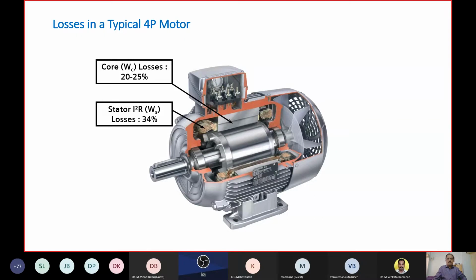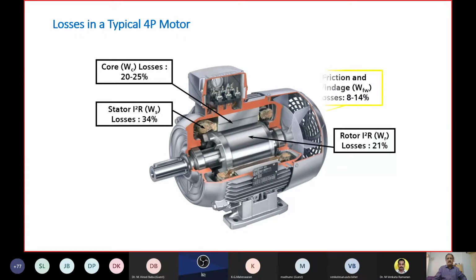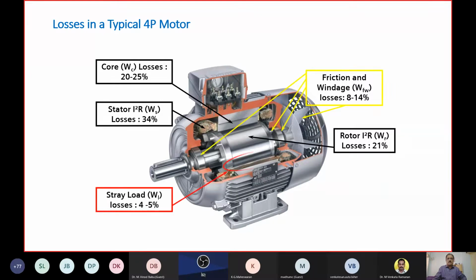Now, what are the typical losses? Most of you in the education field, academic field, will know these are the typical losses in a motor. You have core losses, which is iron losses, which contributes approximately 20 to 25% of the total losses. Stator I squared R, or stator copper losses, is approximately 34%. Rotor losses or rotor copper losses, which is slip losses or air gap losses, is around 21%. Friction and windage losses are sometimes clubbed with the core losses. We call it IFW, iron friction windage losses.